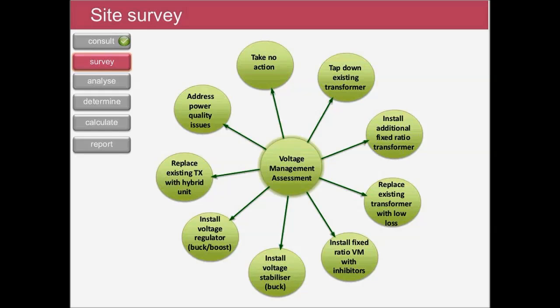So let's take a quick look at some of these possible outcomes deriving from the voltage management assessment. So in the best interests of the consumer, every possible outcome should be considered, and recommendations should be based on experience, engineering due diligence, and above everything else, the client's site-specific requirements. In some cases, we recommend that voltage management is not viable. This could be down to the type of load-bearing equipment on site or the existing voltage levels under typical load conditions.